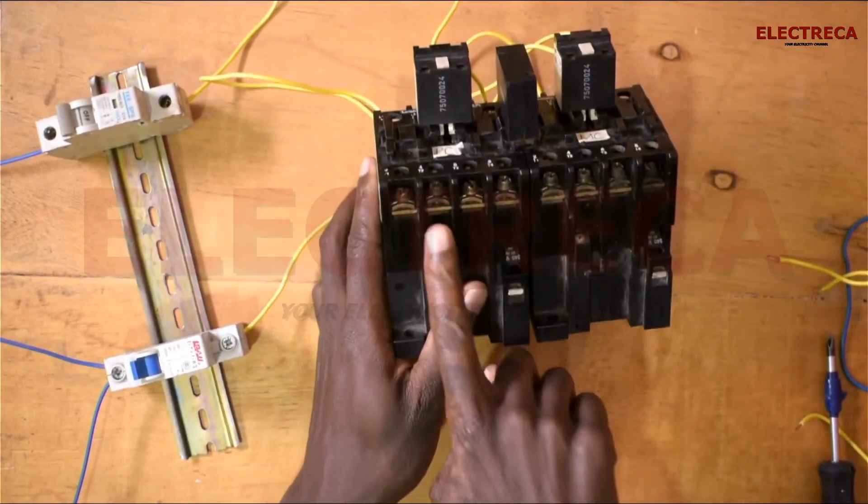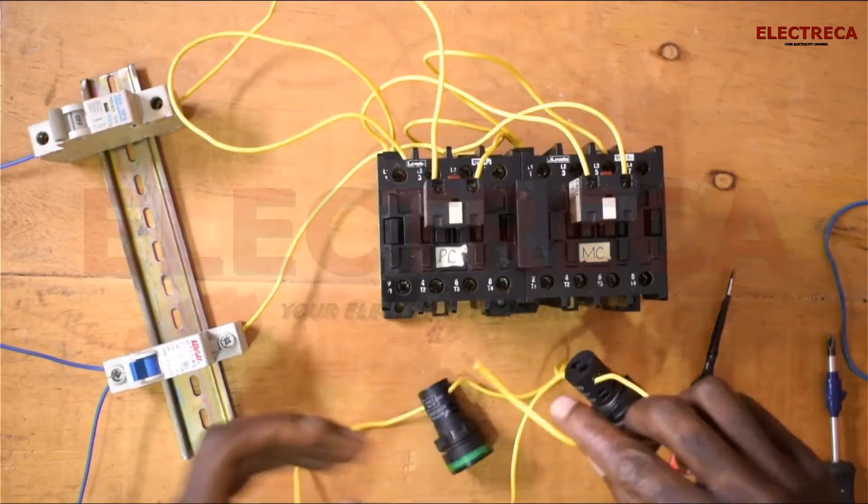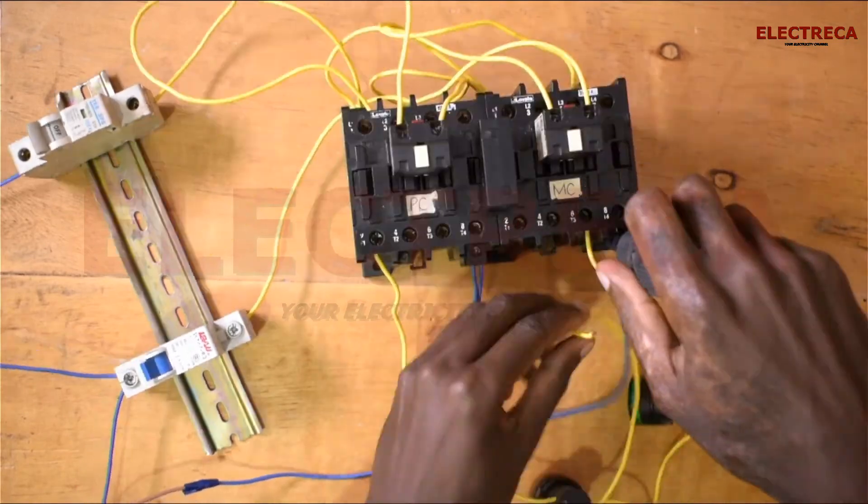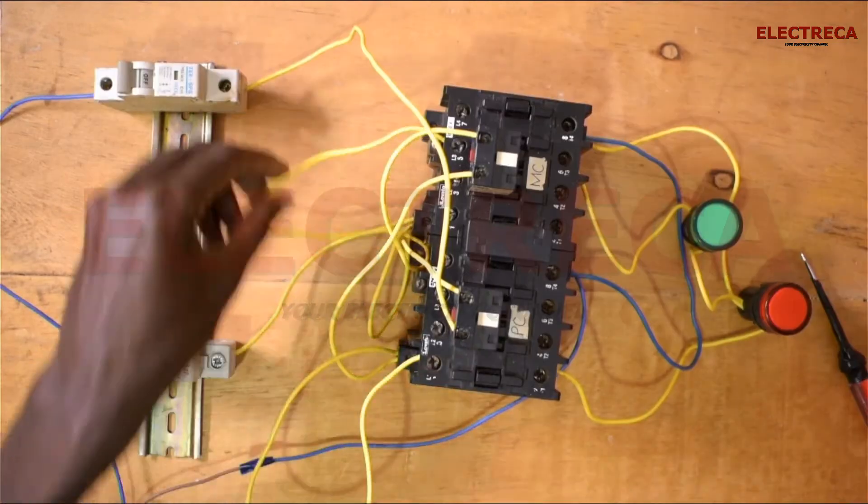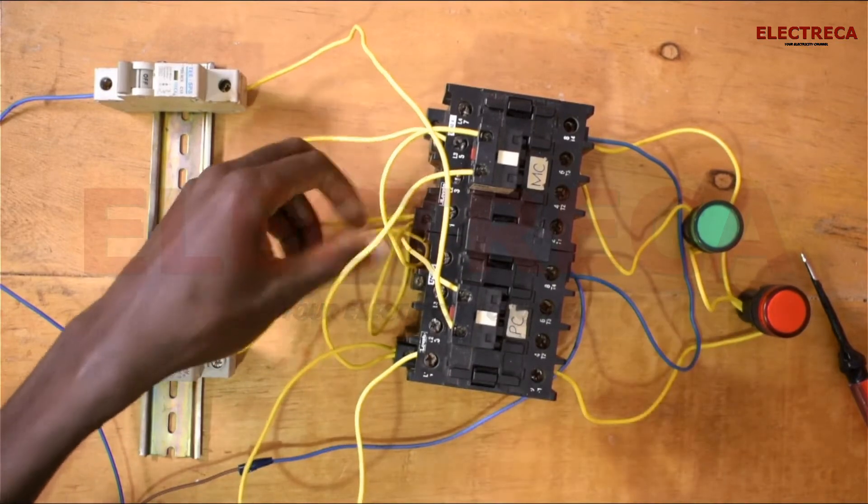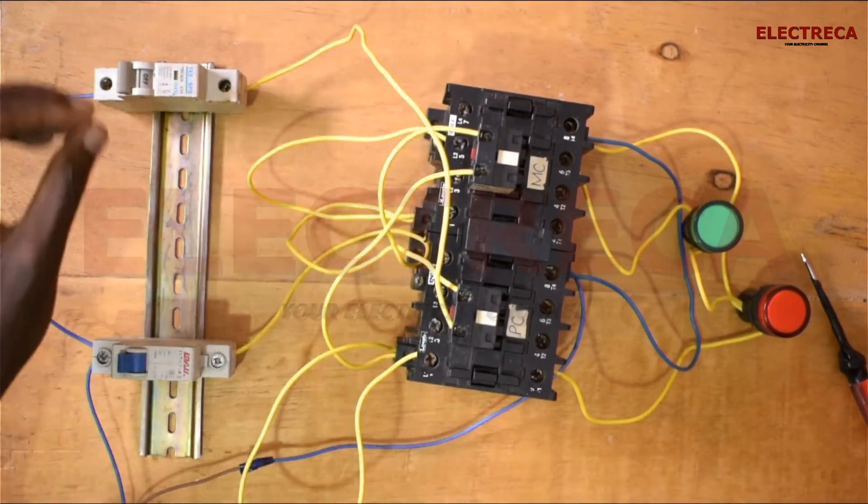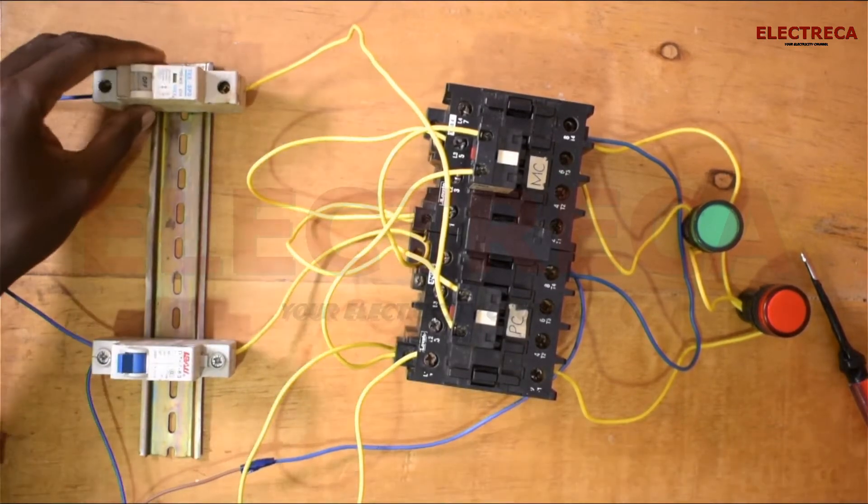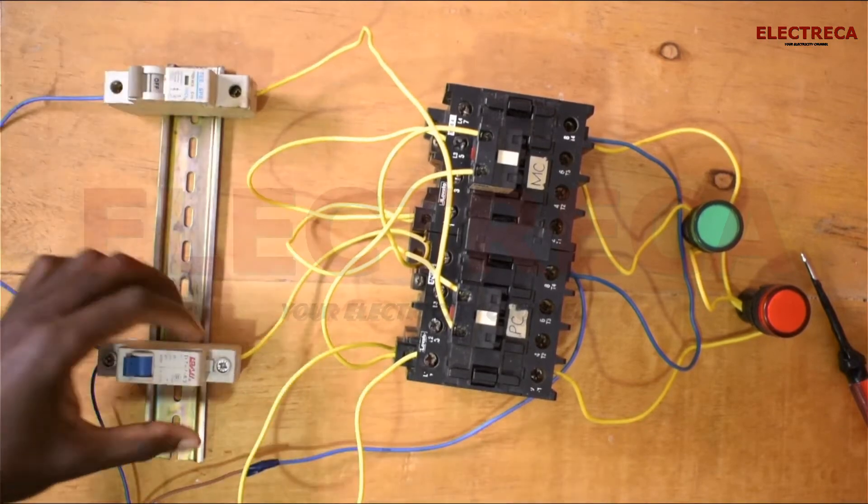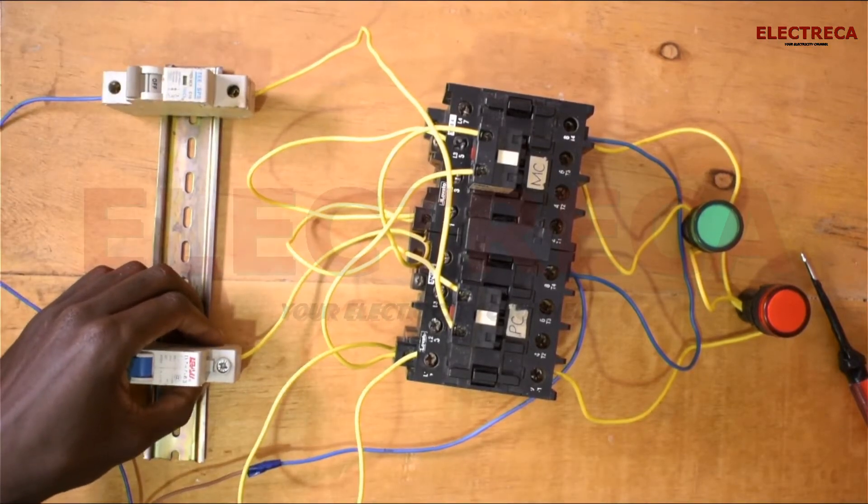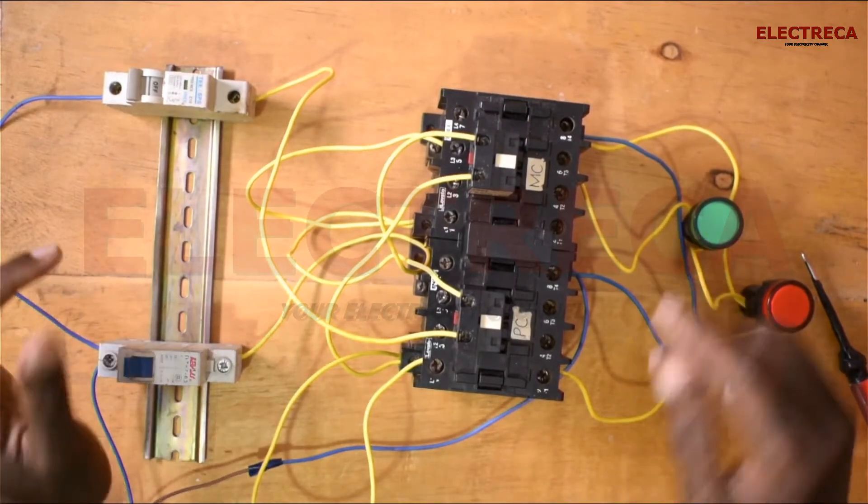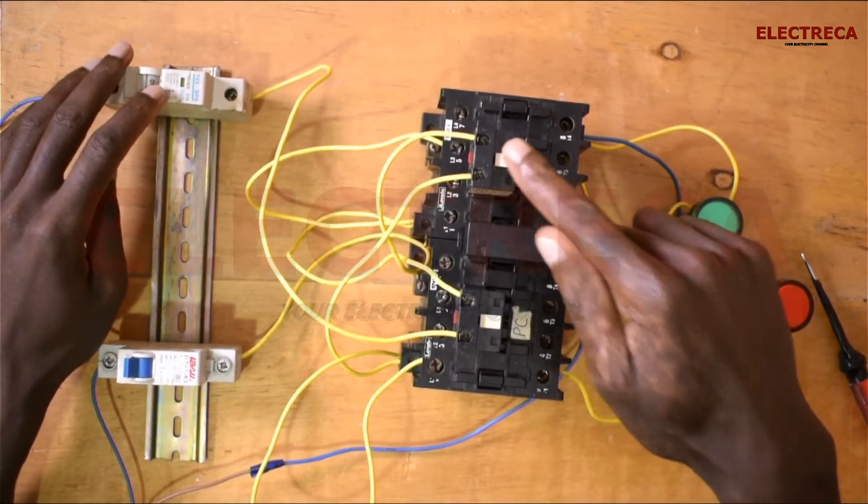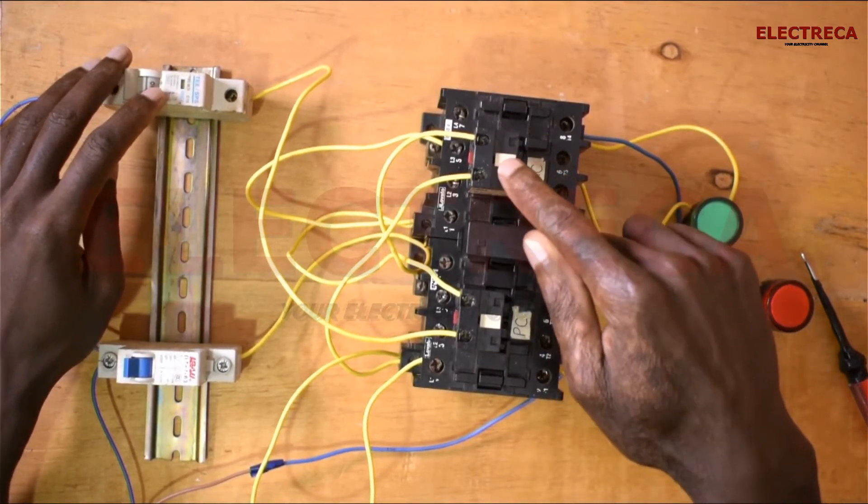So now we have to connect these lights. If you've been following through, this is what we've done. This is a breaker for the main contactor and this is a breaker for the backup contactor. We've used the auxiliary contact. That means for the main contactor to get energized, it has to go through the backup contactor then to the coil.